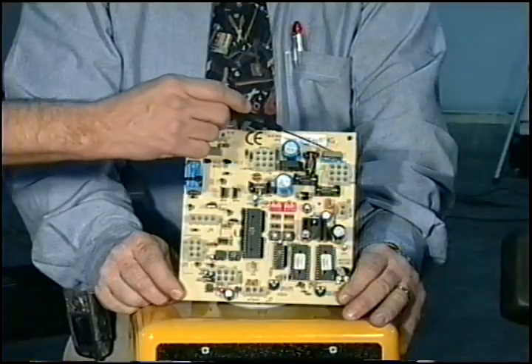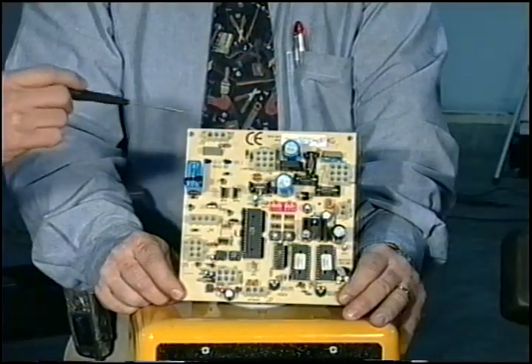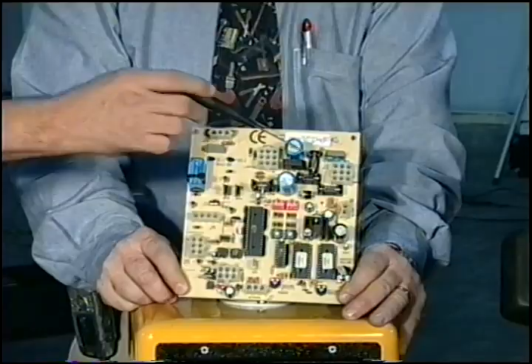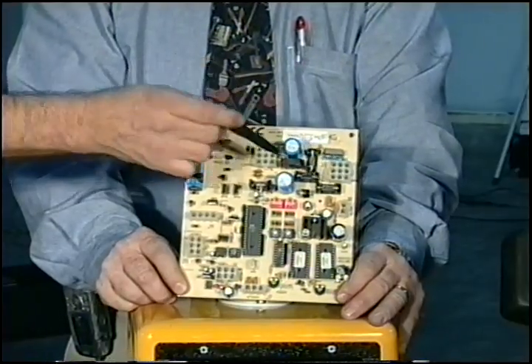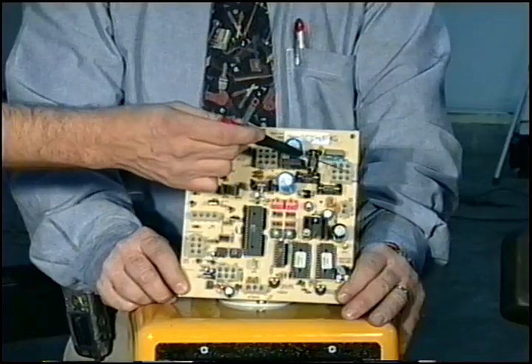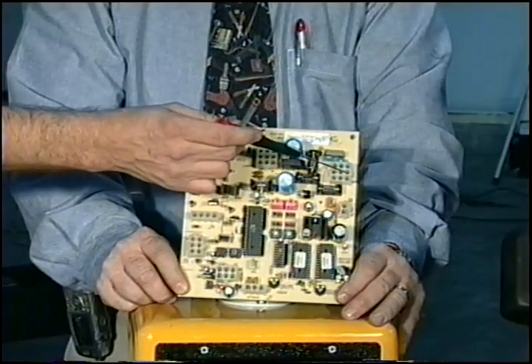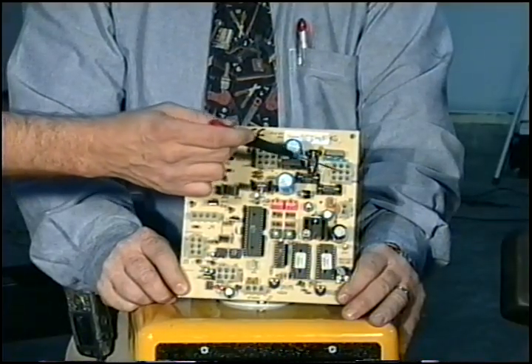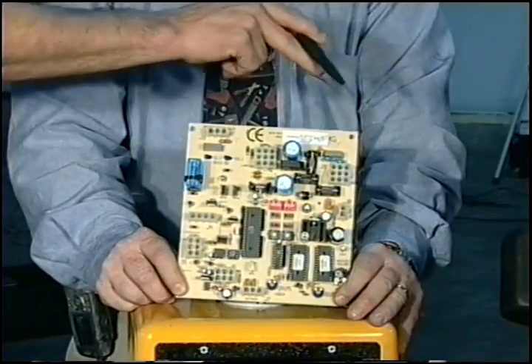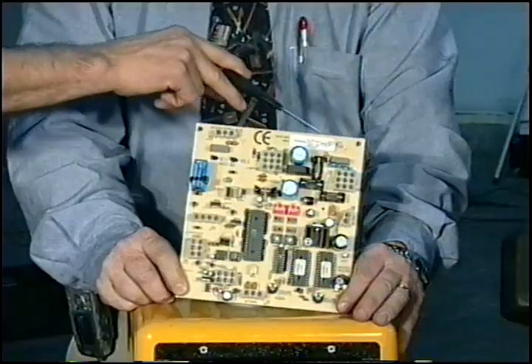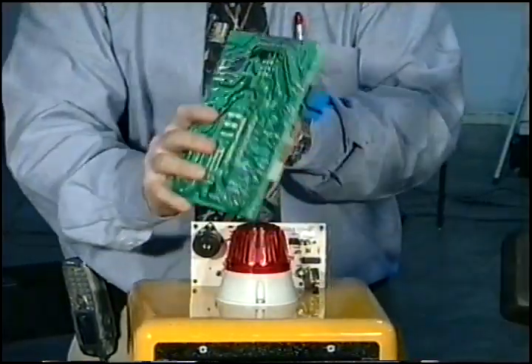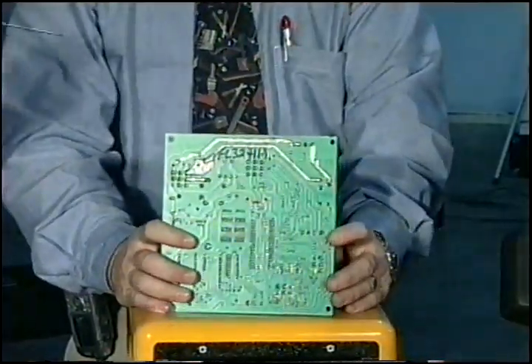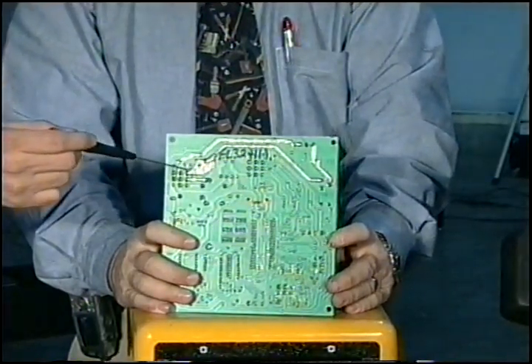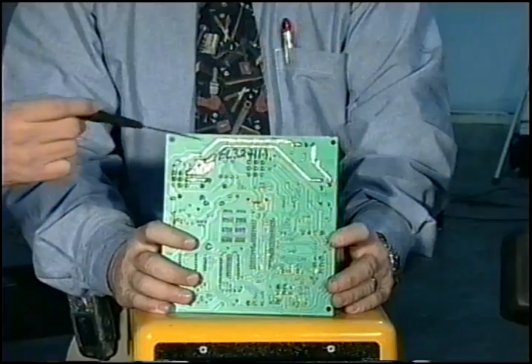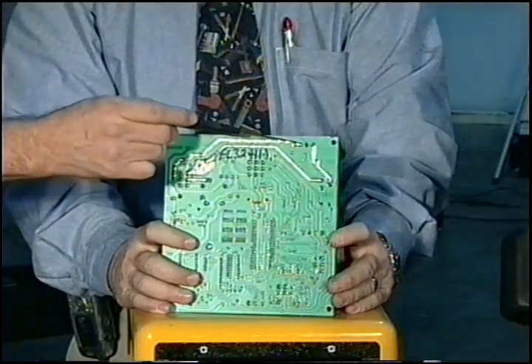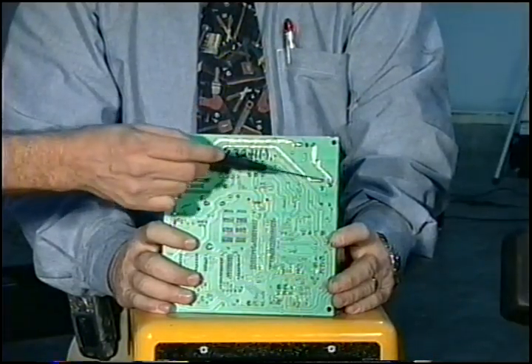Either that, or there's traces on the back of the board that go to this. Your source 120 comes in on connector J1, pins 2 and 8. I might have that reversed. This might be 2 and this might be 8. But it's these 2 pins. That's your 120 supply coming into the board. Then one leg, your neutral side, see, it's these pins right here. And one side is going straight to it. That's your neutral. Then we're switched.